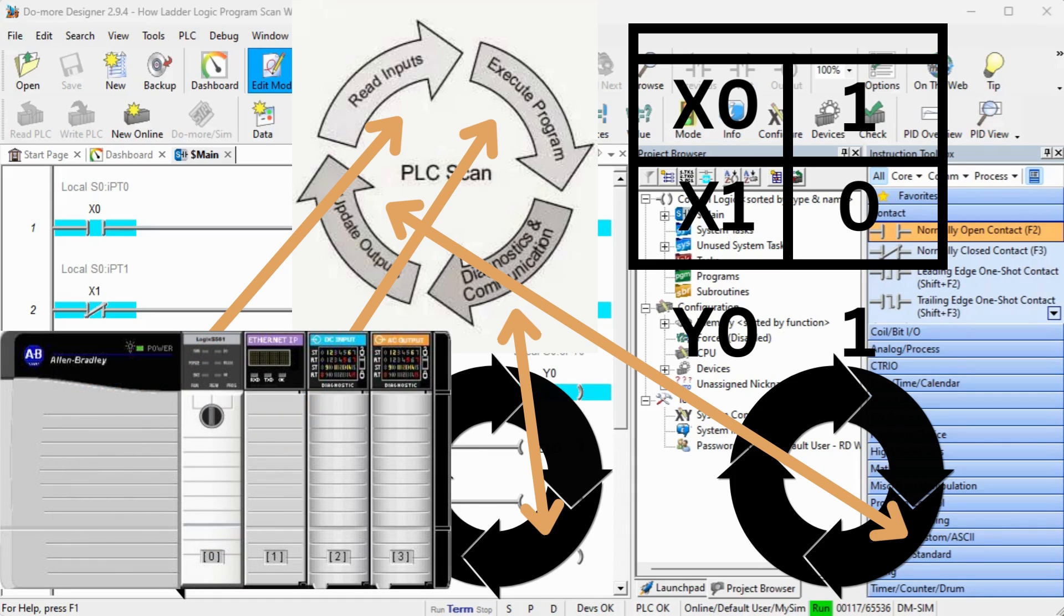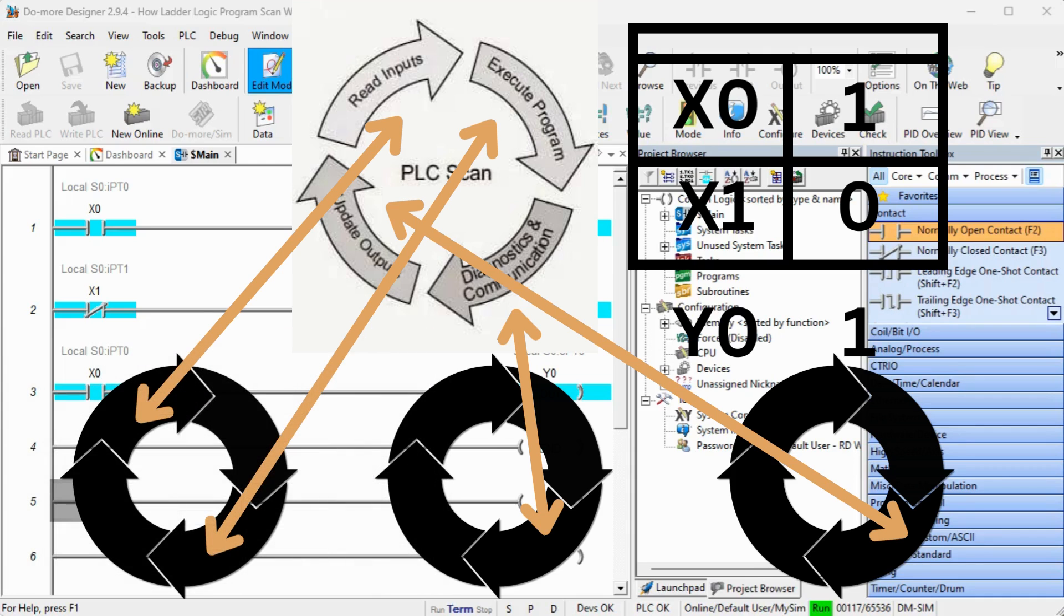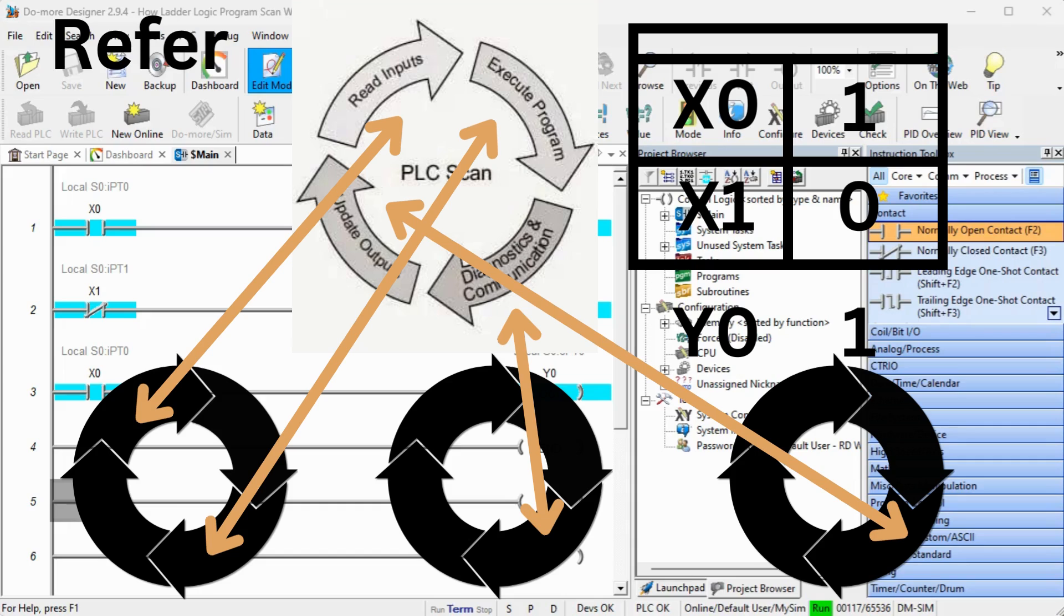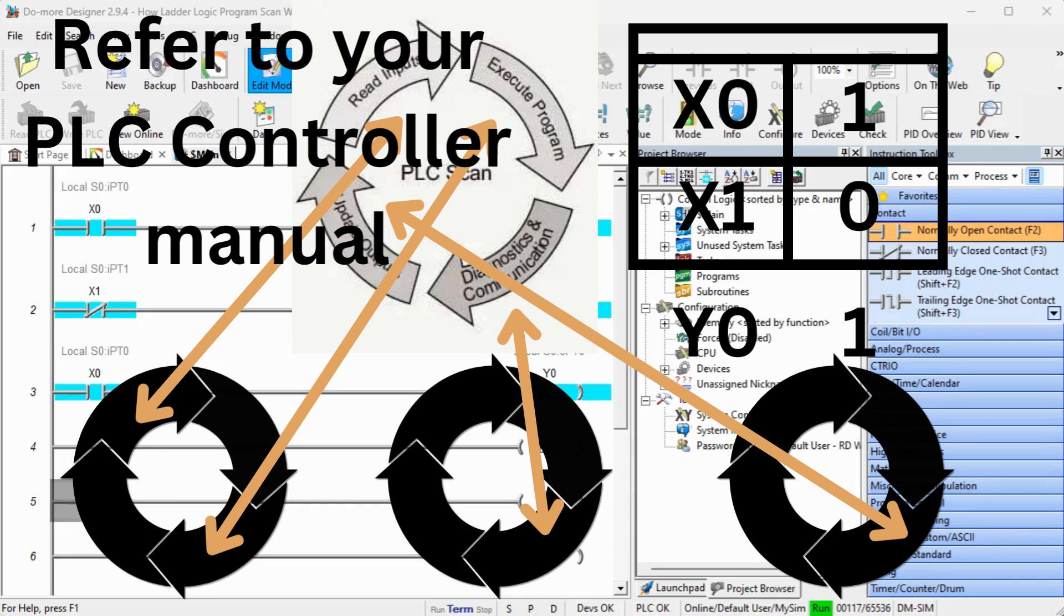Controllers like Allen-Bradley CompactLogix using the RSLogix 5000 software use asynchronous I.O. scan. This means that updating the I.O. table or I.O. memory table will happen whenever possible. In an asynchronous I.O. scan, you typically only use the actual I.O. reference once in your program. Most programmers of these systems will transfer the I.O. to an internal memory first. Then they will use this internal memory in the program code. This will act like a synchronous predictable scan PLC. Please refer to your PLC manual to determine the scanning method of your controller.